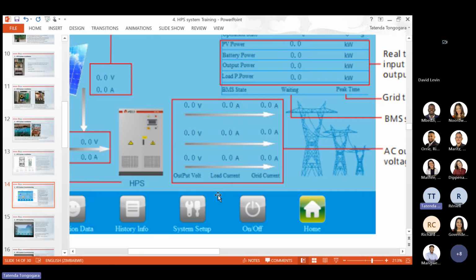When you start up your system using the battery, you configure all the parameters and run it with your load off. If your output voltage is saying 380 or 400 volts, 400, 399, you measure on the AC output on top of the breaker and check if you have the same values. Maybe there's an issue with your system, you can have 400, 400, the sampling is wrong, but on the output you're not getting the 400. So it's always best to measure the voltage before you supply your load.